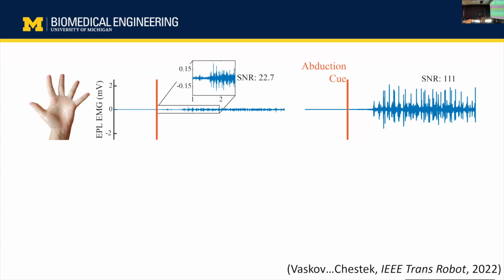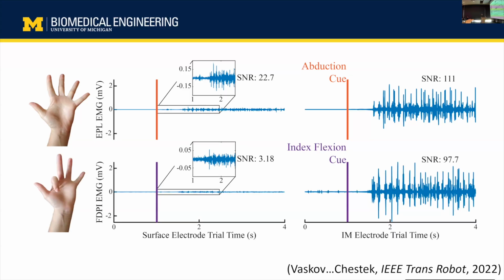However, you don't really see the full benefit until you start looking at muscles that are very difficult to record on the surface of the skin. So for example, FDPI is a really important muscle for flexing the index finger. And it can barely be recorded at all on the surface of the skin. So here, with our measurements, we got an SNR of 3, but with our electrode that is implanted directly into that muscle, we get a signal to noise ratio of 98. So AI is great, but AI can only make things so much better than your physically available signals. I like to think our algorithms are pretty good, but most of what you're seeing is a massive increase in signal to noise ratio of the signals that we are feeding to our AI algorithms.